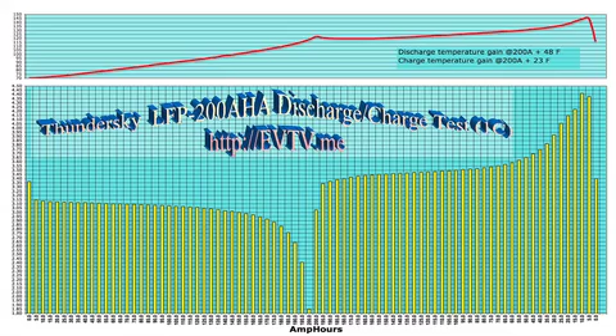We have now reversed our thing and continue our climb on temperature. Right now I'm showing 141 degrees - that's a 61 degree temperature rise from the start of this exercise to the stop. When I ran this the previous time at 70 degrees ambient, by far the huge part of the temperature gain was on discharge. We had a discharge gain of 48 degrees Fahrenheit, and then a further 23 degree Fahrenheit gain on the charge. So charging, even at the same current rate, doesn't seem to cause as much temperature gain as the discharge at 200 amps.